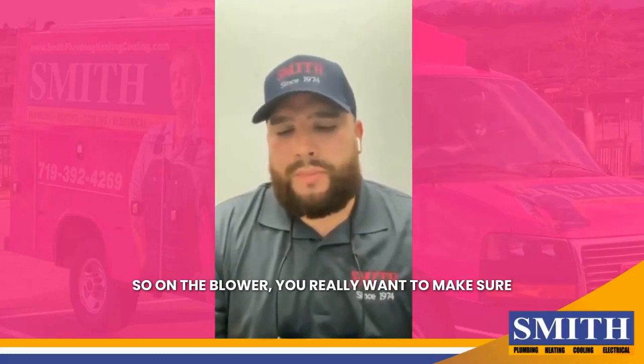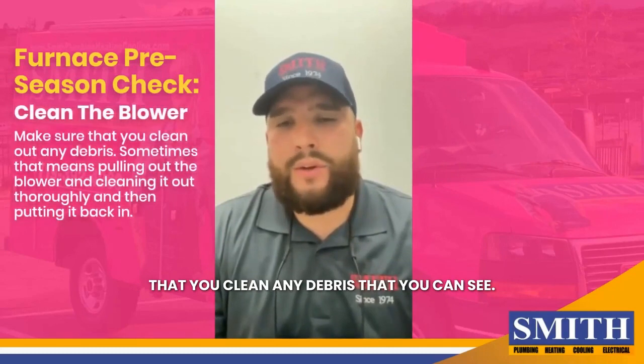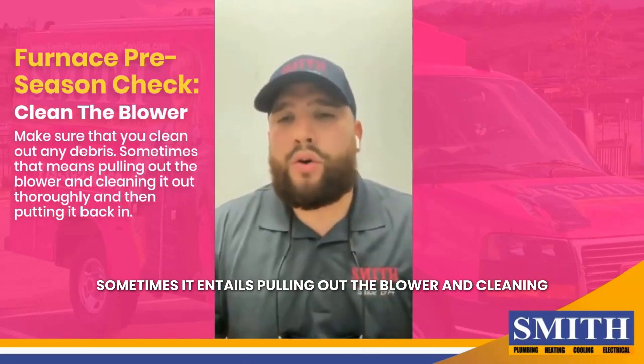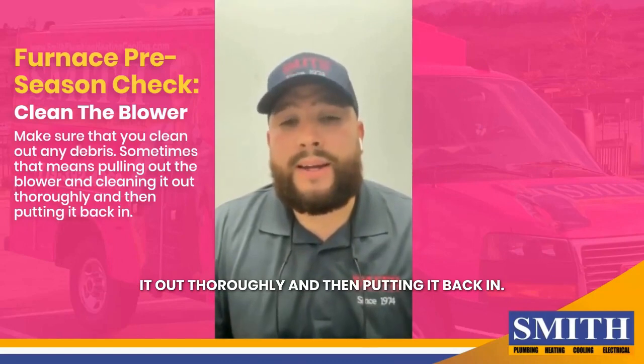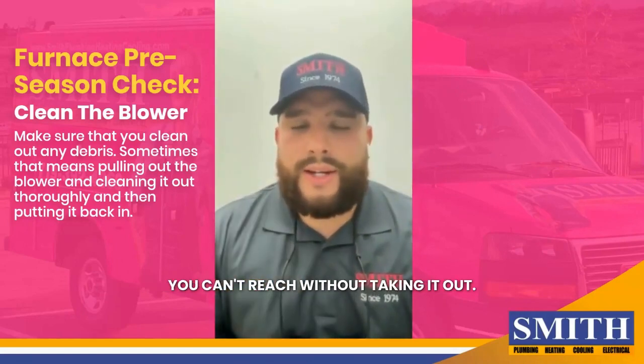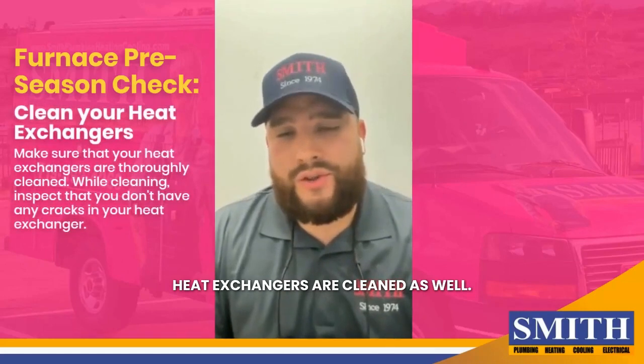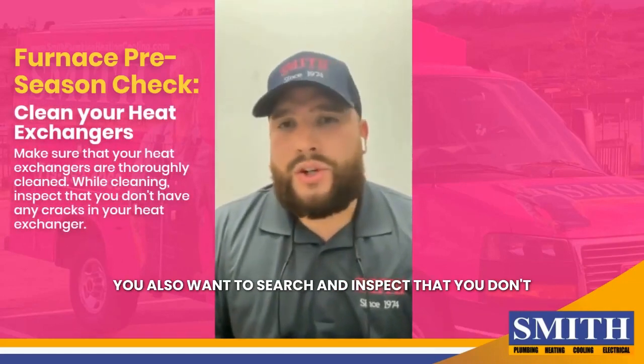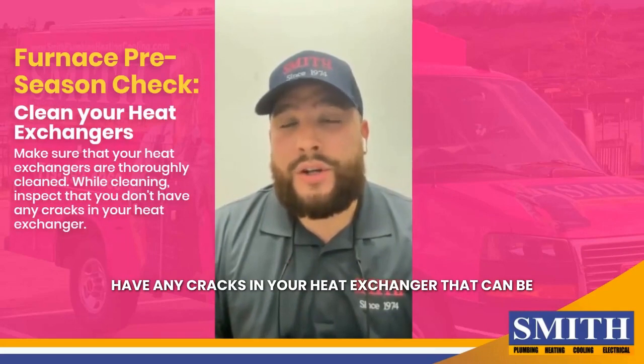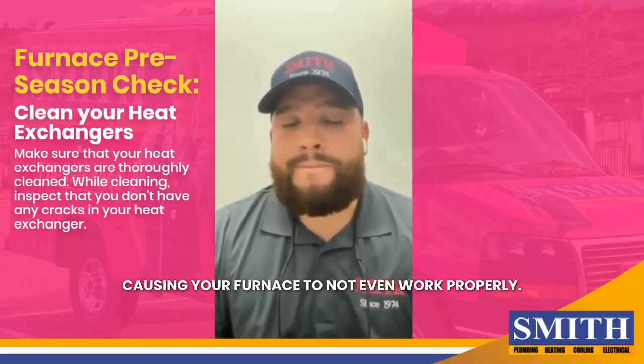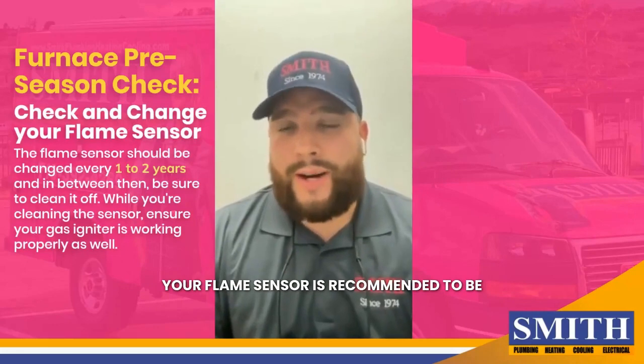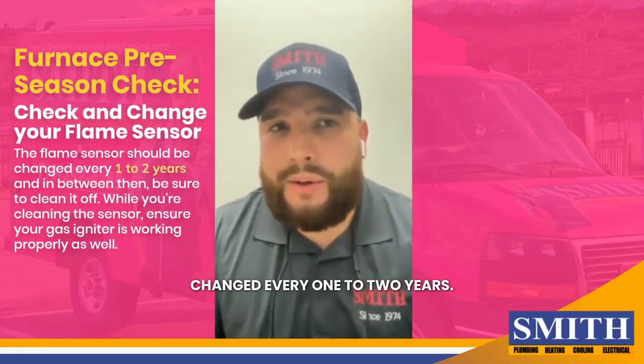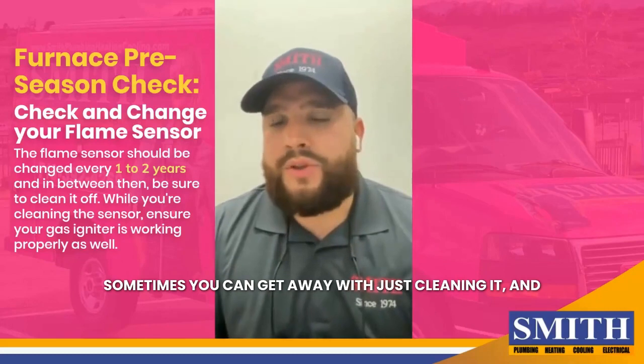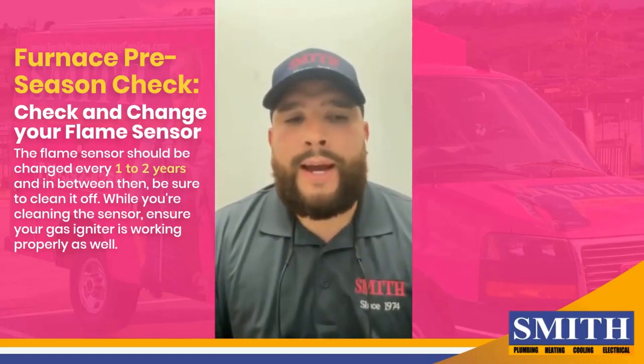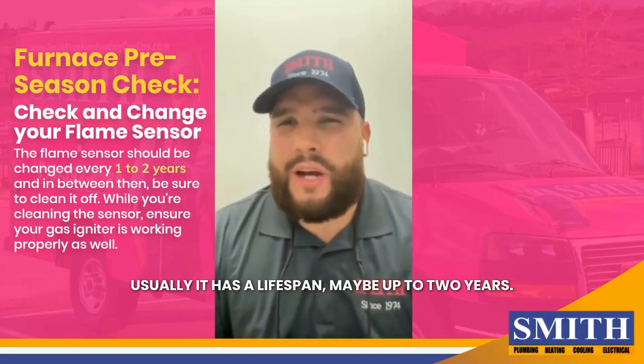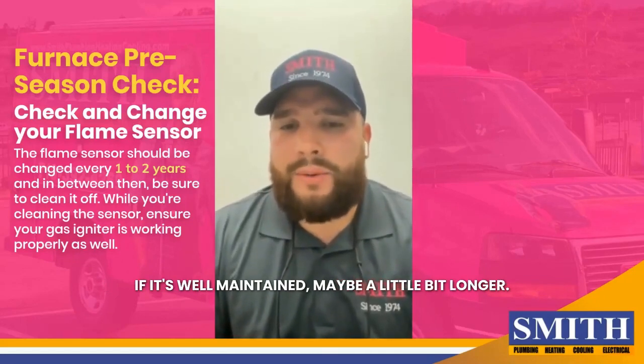Yeah, so on the blower, you really want to make sure that you clean any debris that you can see. Sometimes it entails pulling out the blower and cleaning it out thoroughly and then putting it back in so you don't have that buildup that you can't reach without taking it out. You want to make sure that your heat exchangers are cleaned as well. You also want to inspect that you don't have any cracks in your heat exchanger that can be causing your furnace to not even work properly. Your flame sensor is recommended to be changed every 1 to 2 years. Sometimes you can get away with just cleaning it, and usually it has a lifespan of maybe up to 2 years. If it's well maintained, maybe a little bit longer.